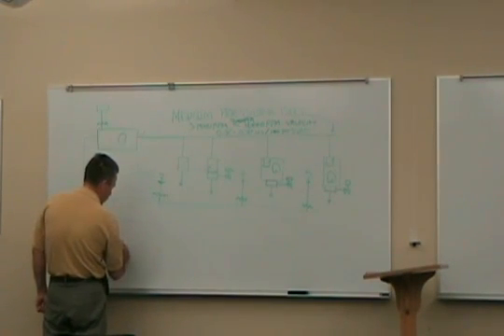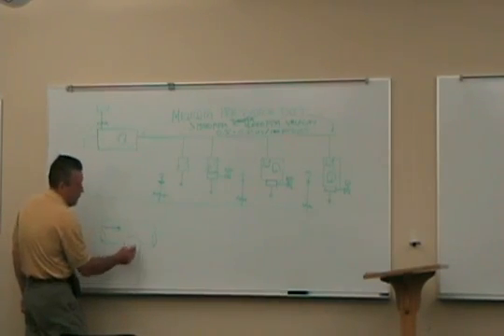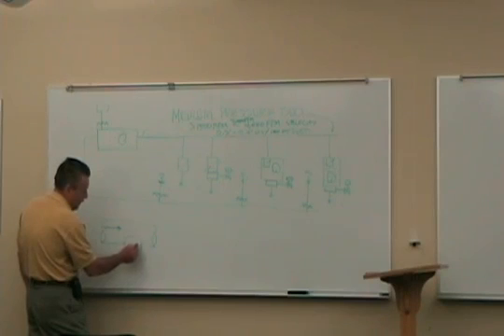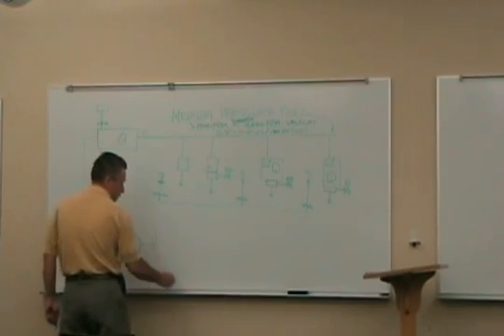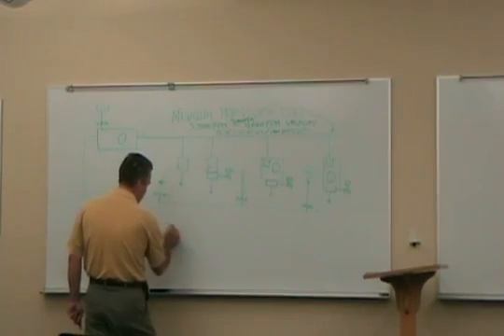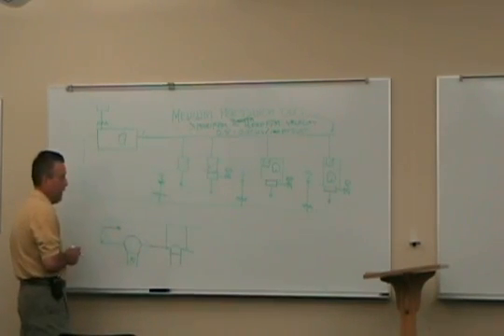In the spiral duct, you'll see fittings that are called conical. So you've got an airstream going down through here. That air has to turn and go out to a VAV box. And this duct may be 8-inch, and you have a slightly wider opening so the velocity is slower here till it gets into this duct. And that fitting right there, versus a fitting like that, would probably have 4 times less pressure drop than a fitting like that right there. So you very seldom would ever see a straight tap like that on high pressure duct.